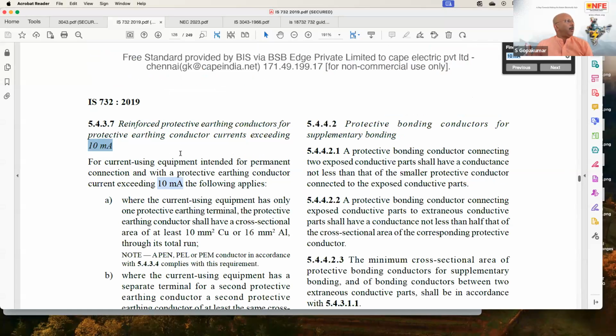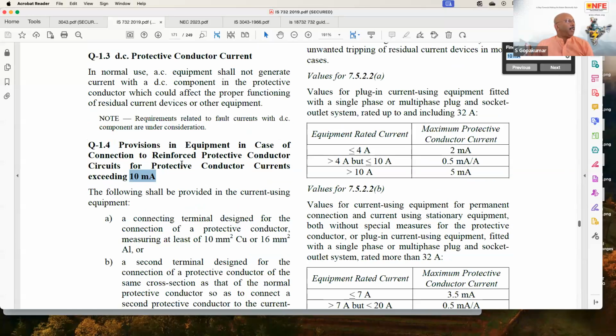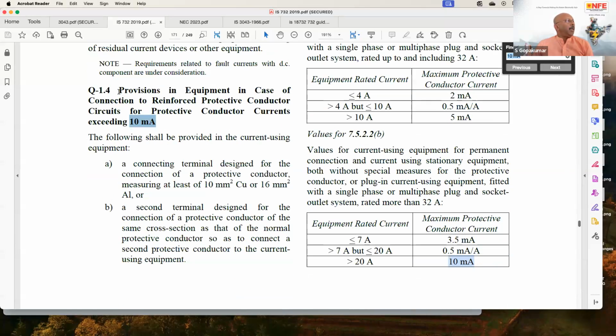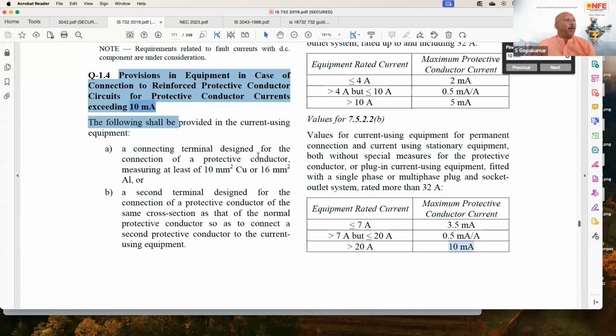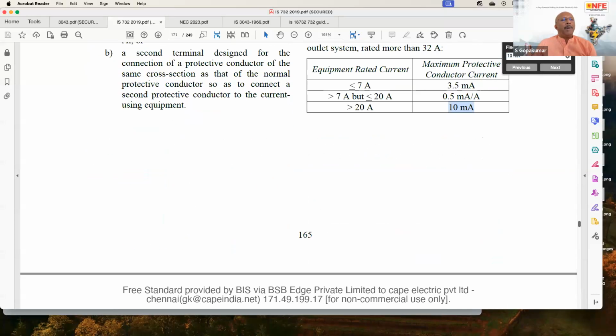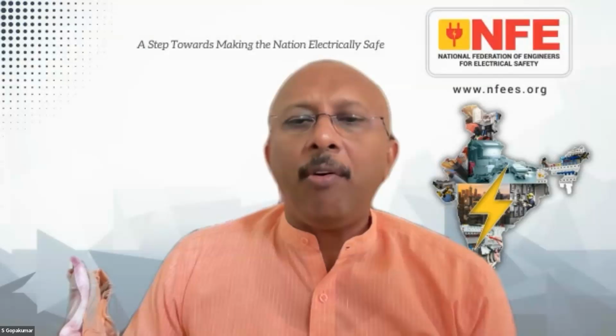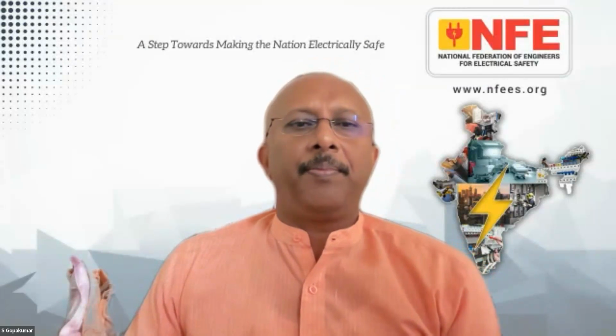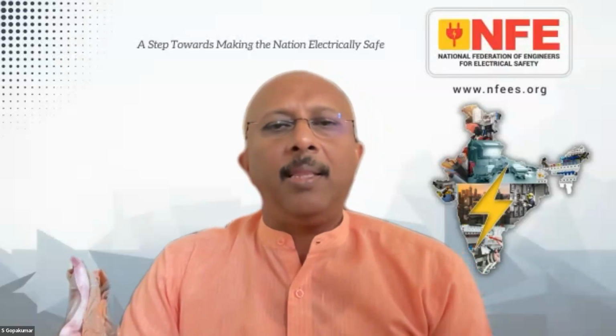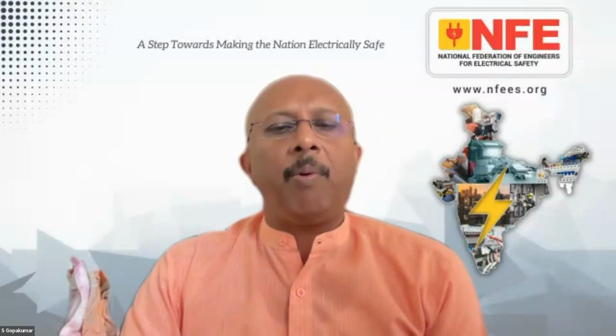So if you search on 5.4.3.7, how to make a reinforced protective conductor, and then search further, you see the provision. This is annexure Q, provision in equipment in case it is exceeding 10 milliampere. So all these are already there in the standard. The manufacturers are already taking care of it in their design. As a result, leakage is not going to create a problem to people.